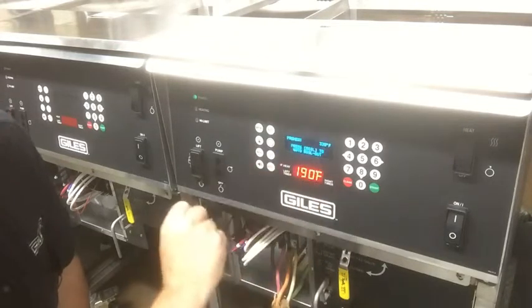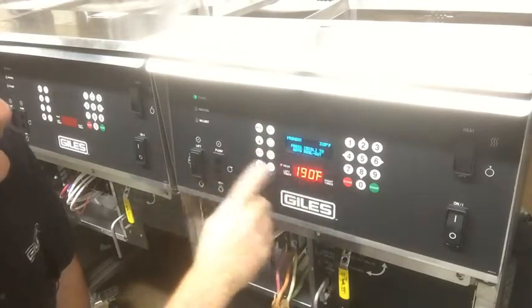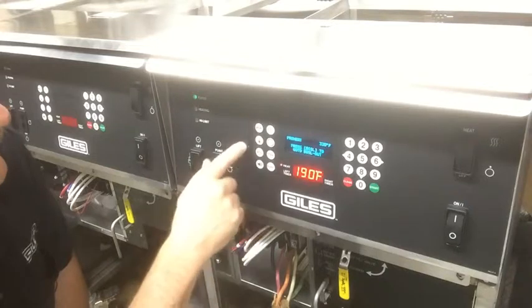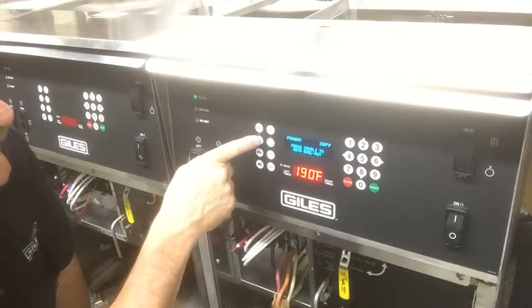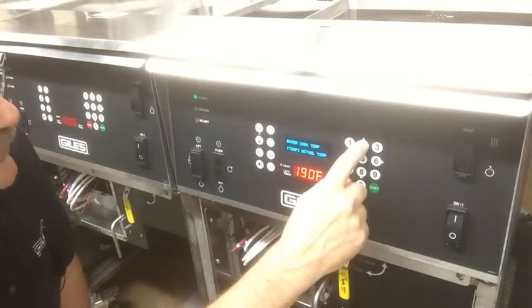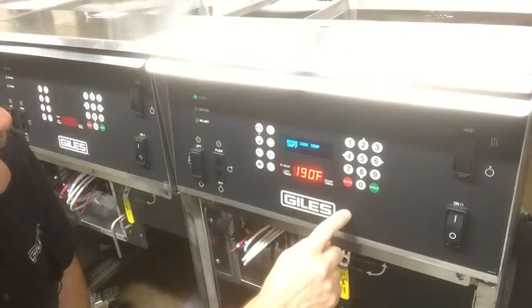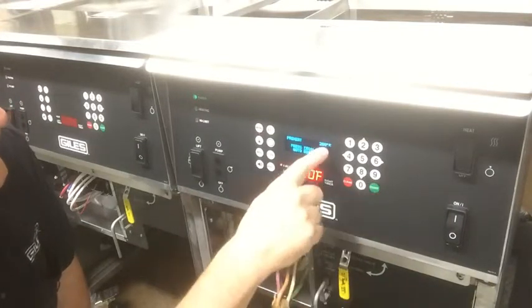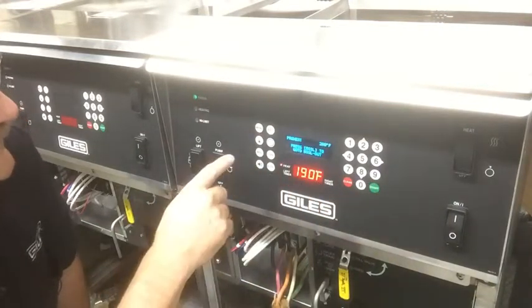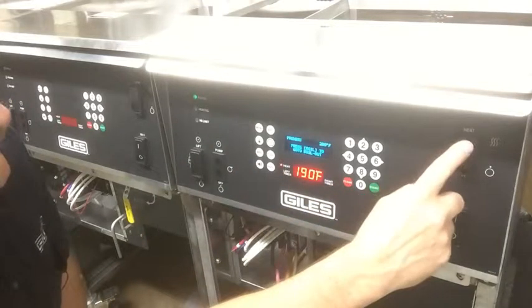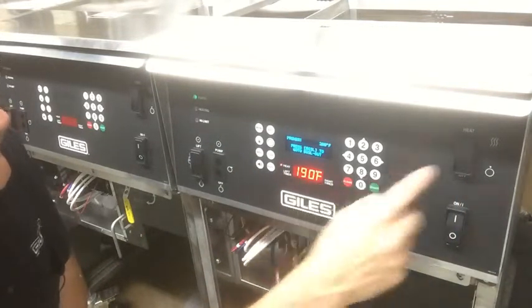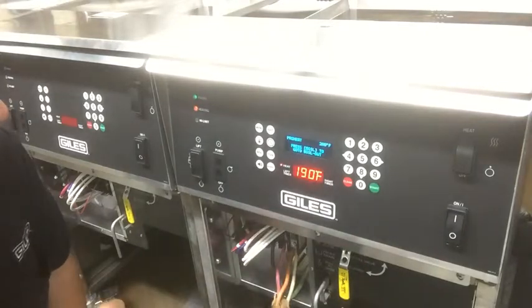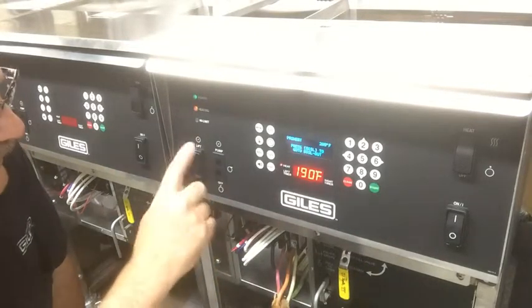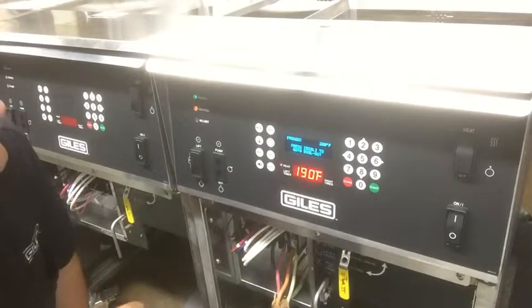Right now I've got it set to a preheat of 335. I'm going to bump that down, and to do that I'm going to press my temperature button and put in 200 and start. Okay, now it's set to 200 degrees. So I'm going to go ahead and turn my heat on, and if you watch here you'll see that slowly start to build up in just a minute. But we're going to go ahead and bring that up.